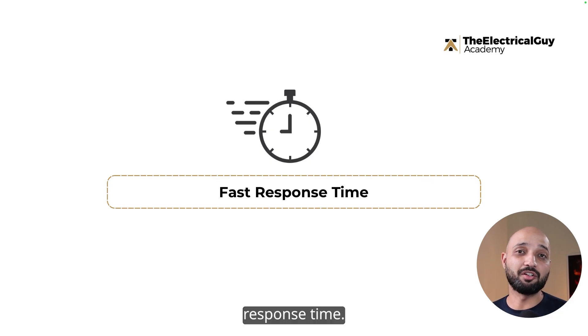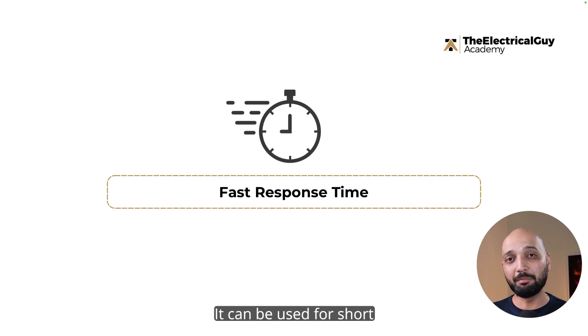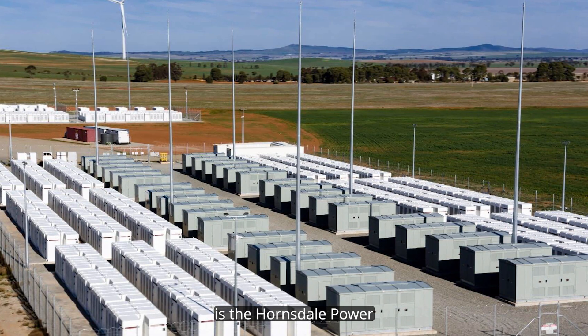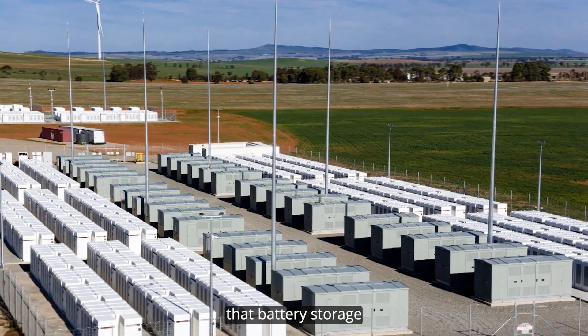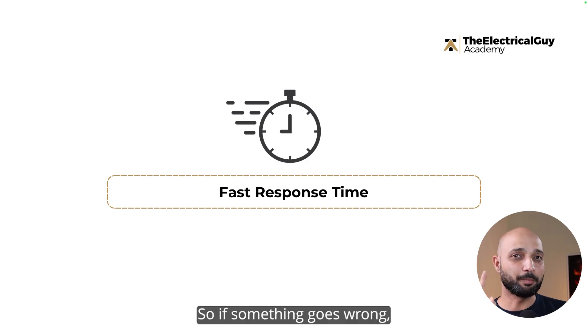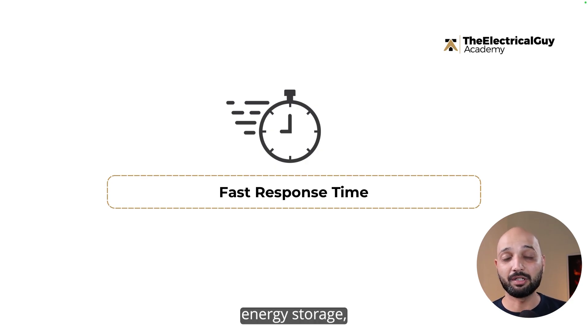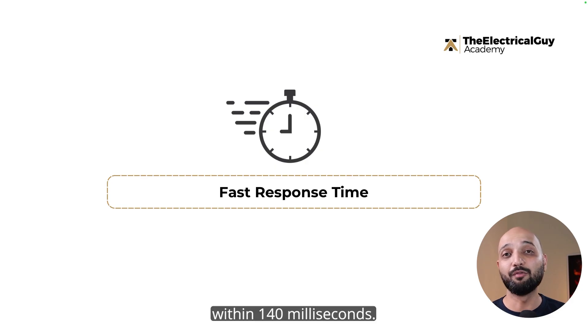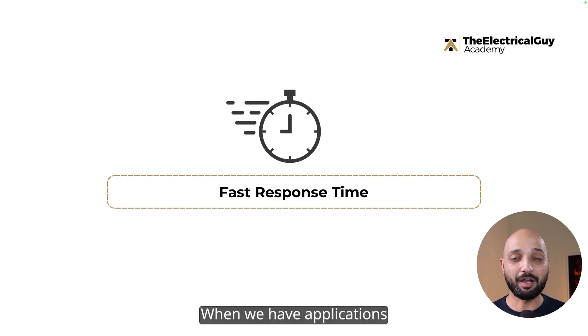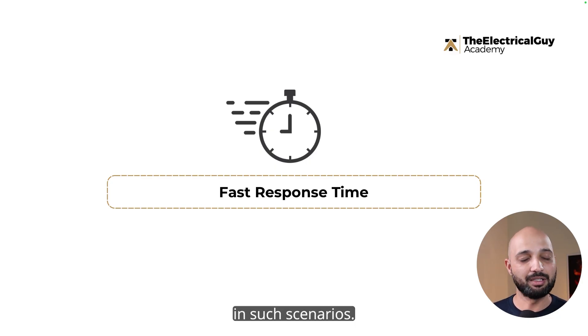Battery storage also has a faster response time, making it useful for both short and long duration storage. One ideal example is the Hornsdale Power Reserve in South Australia, which can reportedly respond within 140 milliseconds. If something goes wrong and you need output from the battery energy storage, it will be available to the grid within 140 milliseconds — which is really, really fast. This fast response time is critical for applications like frequency control, frequency support, and voltage balancing.